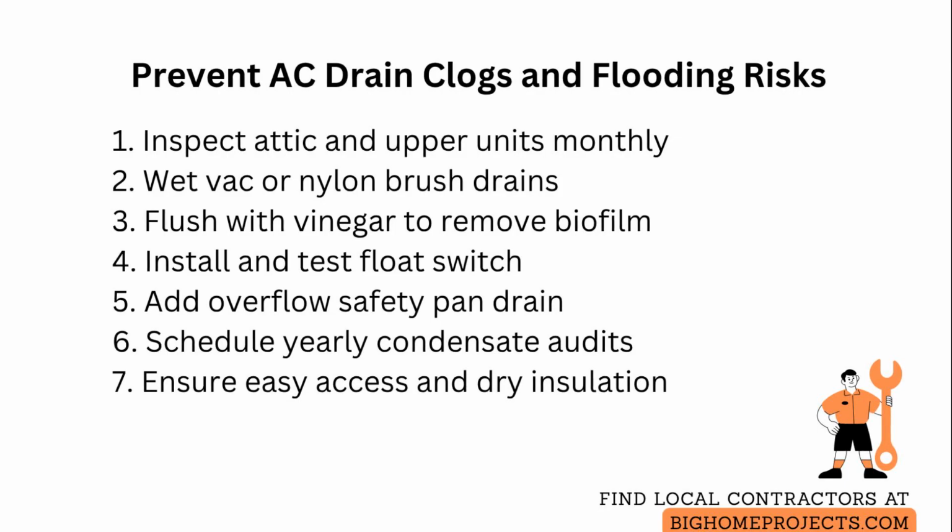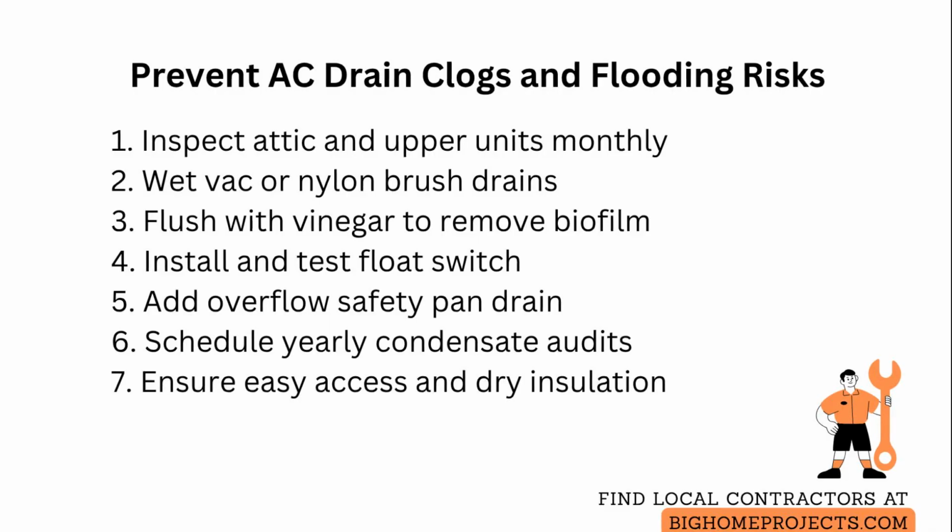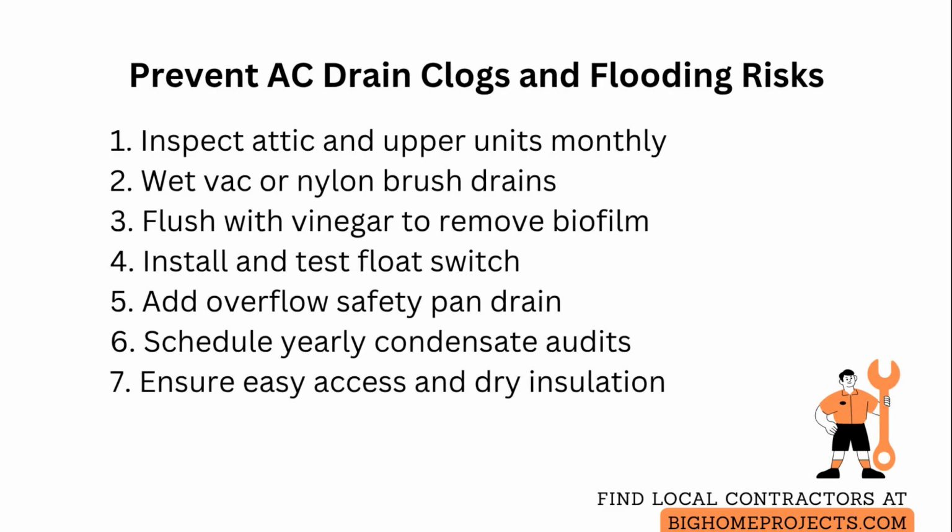Fit a float switch in the drain pan that cuts power to the compressor when water rises, and test that switch by pouring water into the pan until it trips. Replace any switch that does not reliably cut power.